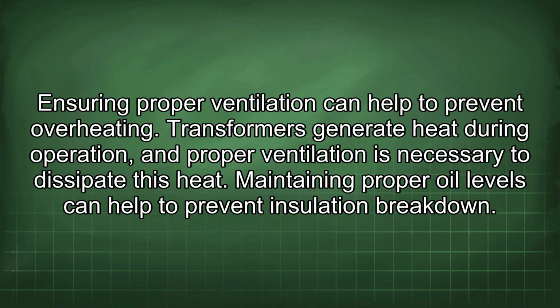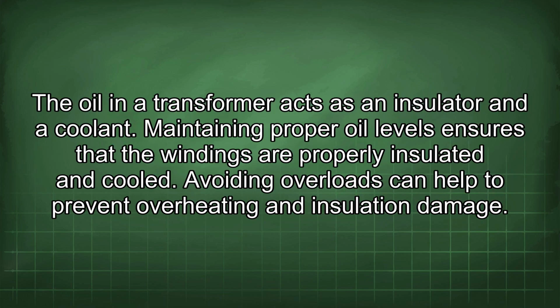Ensuring proper ventilation can help to prevent overheating. Transformers generate heat during operation, and proper ventilation is necessary to dissipate this heat. Maintaining proper oil levels can help to prevent insulation breakdown. The oil in a transformer acts as an insulator and a coolant. Maintaining proper oil levels ensures that the windings are properly insulated and cooled.